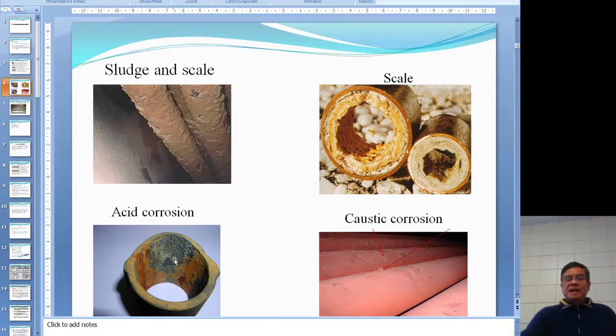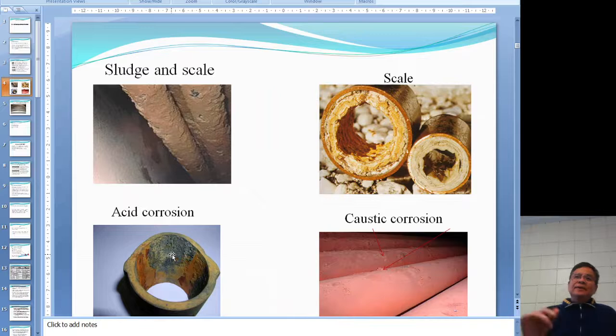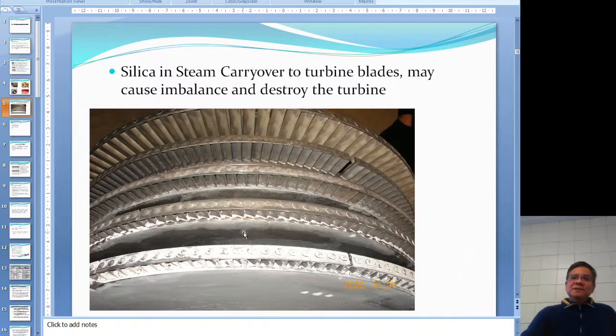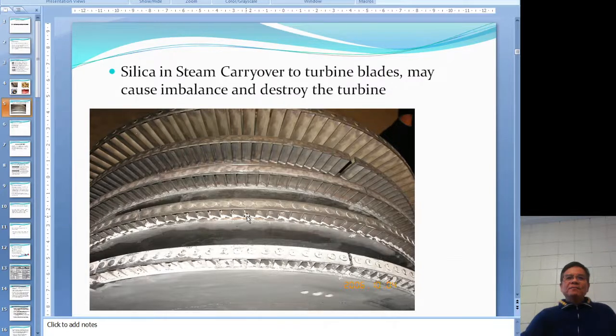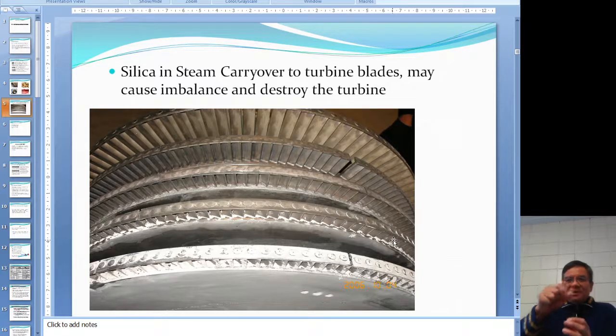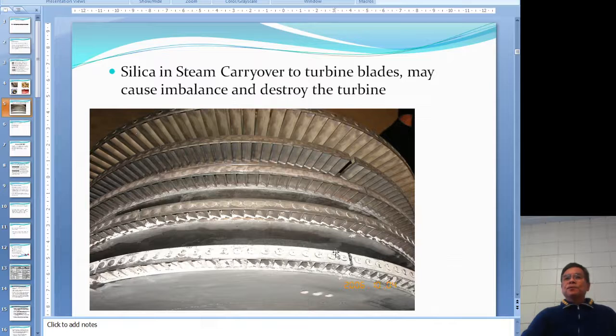The black spots represent acid corrosion where metal has been eaten away. Another type shown is caustic corrosion. The next image shows a turbine blade — you can see significant deposits on the blade. Turbine blades turn at very high speed, sometimes up to 15,000 RPM. Any imbalance can cause the blade to hit the housing and ruin the turbine.